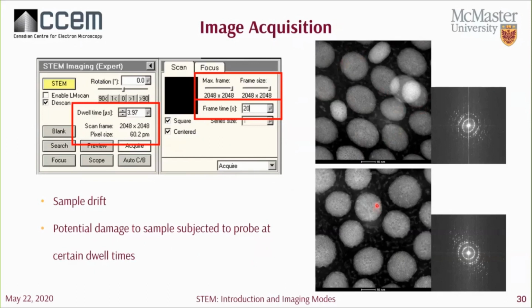And here we have a more representative sample, in which you wait a little bit more and then acquire your image. You have to play around with your magnification and your dwell time to figure out the right imaging conditions. The fastest way to test this, I would say, is to test it in your session and see what kind of images you get. But you'll have to think about the potential to damage your sample while you're testing these parameters. So it's good to either have a test sample at first, or have a large sample area so that you can test these parameters in regions that are not of interest to you before taking a final perfect image.